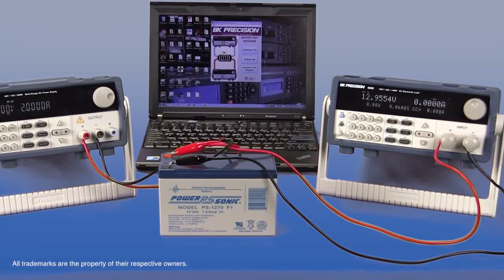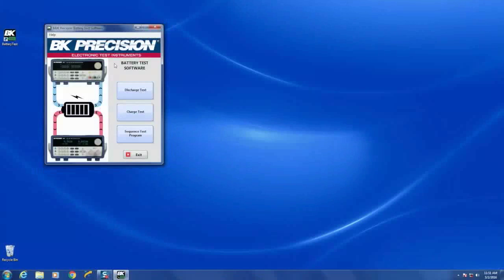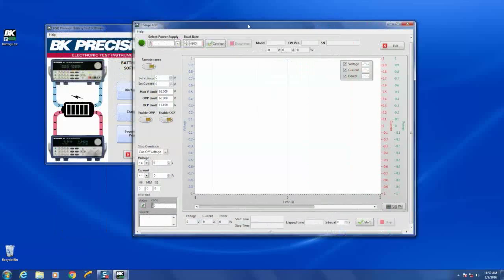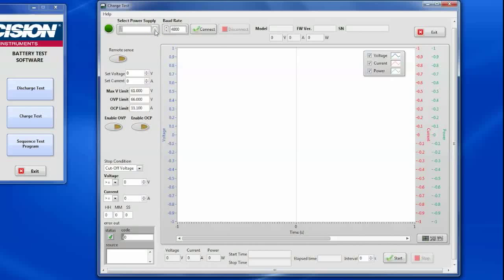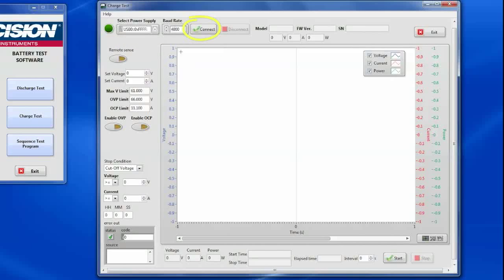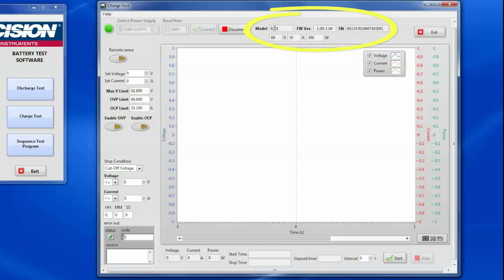To start with, what we're going to do first is make sure that the battery we've got here off camera is fully charged. I'll go to the charge test and open the control panel window for the charge test power supply. Got a power supply selected here in the USB port. It says it's the 9200 series. I'll select that and click connect. There you can see we've got the 9201, the firmware version, the serial number, all of the power supply information is up here.